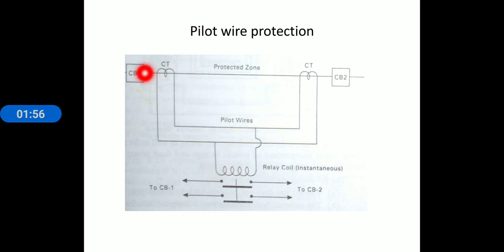But whenever a fault occurs in this line, the entering current of this line is unequal to the leaving current of this line. At that time, the differential current flows through this relay. Then the relay sends a signal to the circuit breaker, and the circuit breaker operates, trips the circuit and isolates the faulty section. That is the general pilot wire protection.